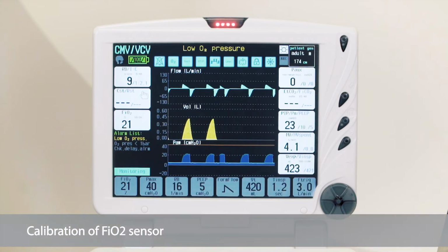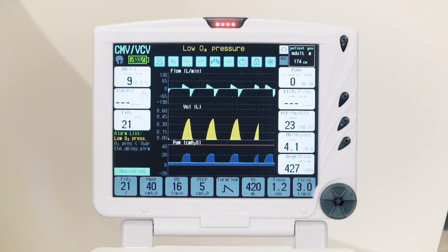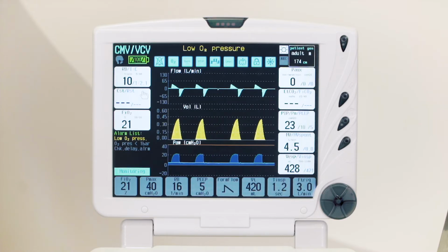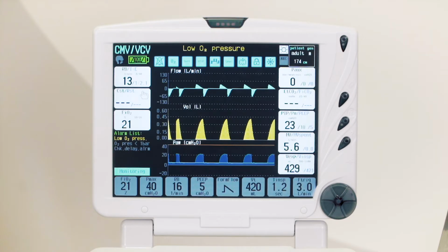Calibration of FiO2 sensor. Calibration of the oxygen sensor measuring the concentration in the inspiratory gas, FiO2, is used during maintenance, after replacement of the FiO2 sensor, according to the method, to check or replace the oxygen sensor during automatic control and calibration of the FiO2 sensor, or in any cases, particularly if the concentration measurement error exceeds 2% during air ventilation.